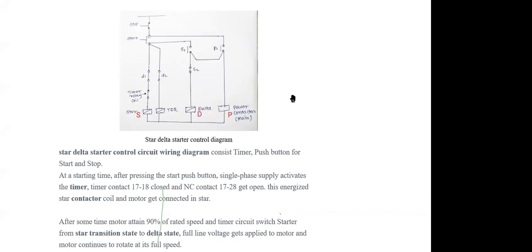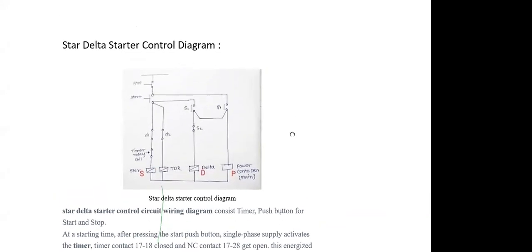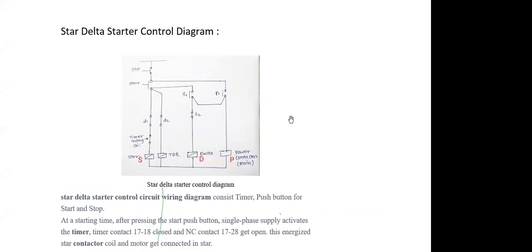this is the star delta starter control circuit. So when we start the motor, this start circuit and main circuit get energized. Keep in mind, this is a single phase control circuit shown. It is not a power circuit, but as the control circuit picks up, the 3-phase contactor gets energized.